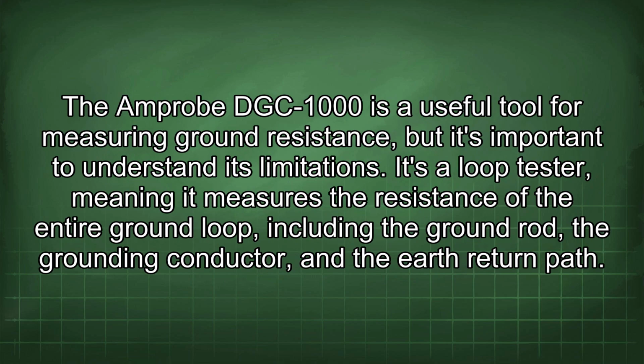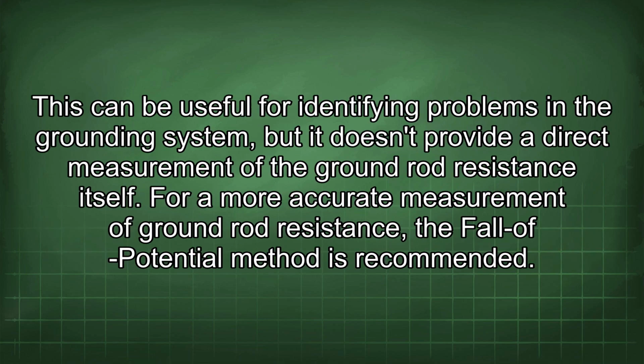The Amprobe DGC-1000 is a useful tool for measuring ground resistance, but it's important to understand its limitations. It's a loop tester, meaning it measures the resistance of the entire ground loop, including the ground rod, the grounding conductor, and the earth return path. This can be useful for identifying problems in the grounding system, but it doesn't provide a direct measurement of the ground rod resistance itself. For a more accurate measurement of ground rod resistance, the fall-of-potential method is recommended.